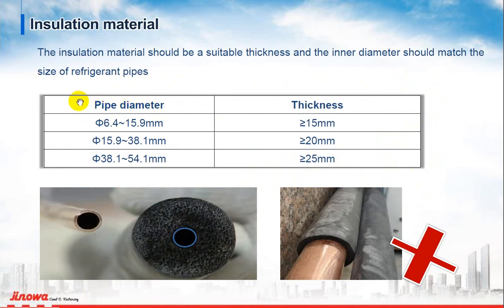For copper pipe diameter from 6.4 to 15.9 millimeters, your insulation thickness must be 15 millimeters or more.